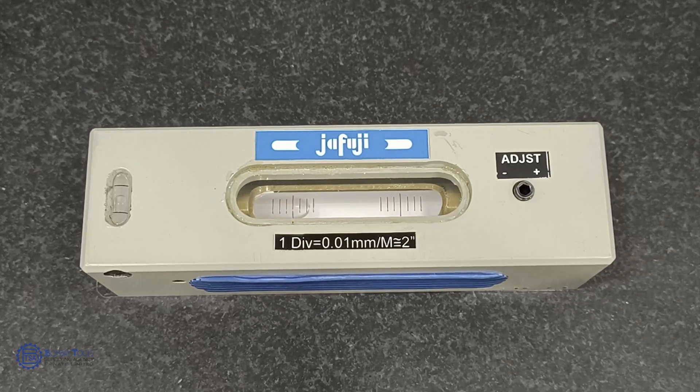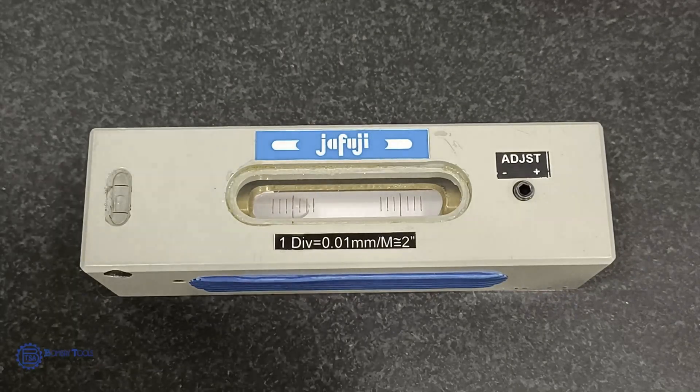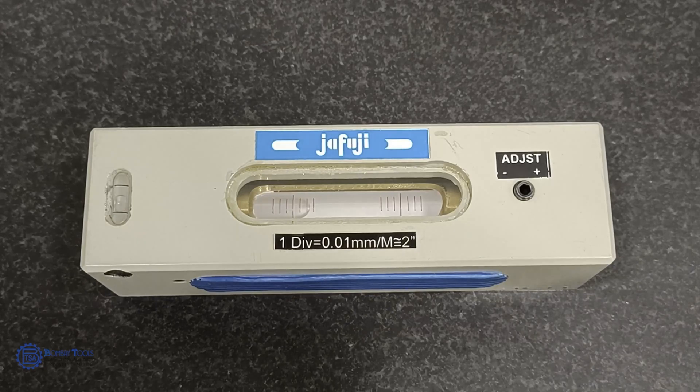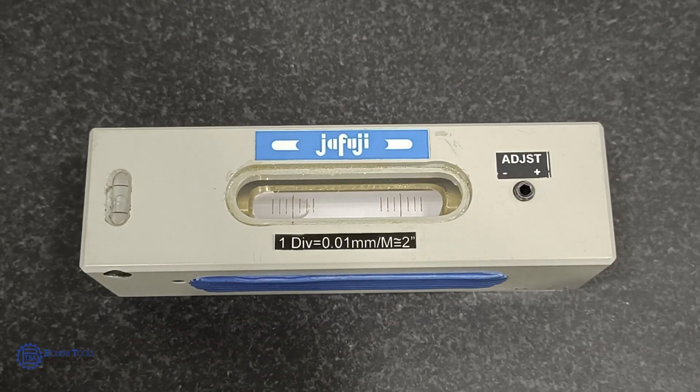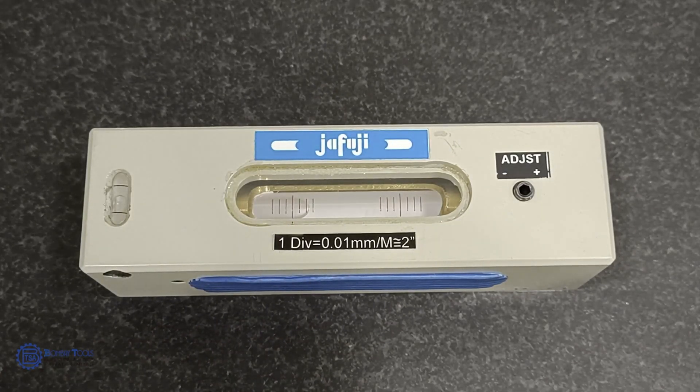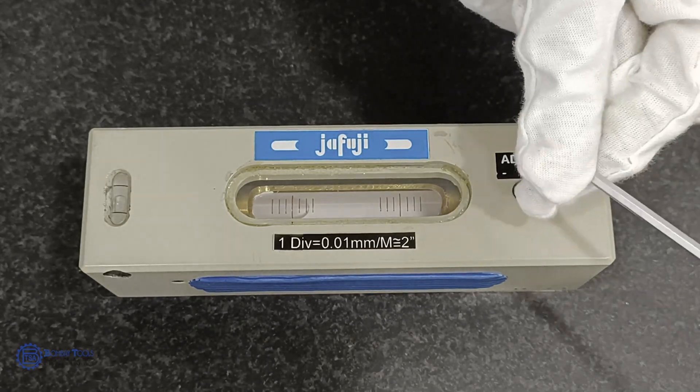The speciality of Jafuji's precision levels is that the geometry of the base is adjusted exactly parallel to the vial axis by grinding and scraping. The bubble in the spirit level will always move along the radius of the tube for a certain distance depending on the tilt. An Allen screw is also provided to do zero setting of the bubble.